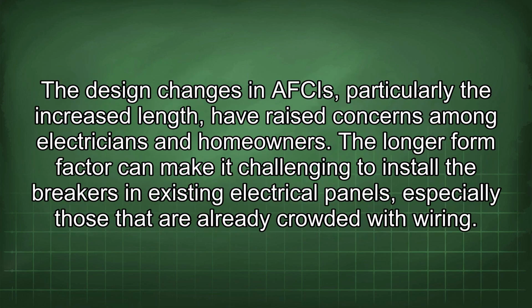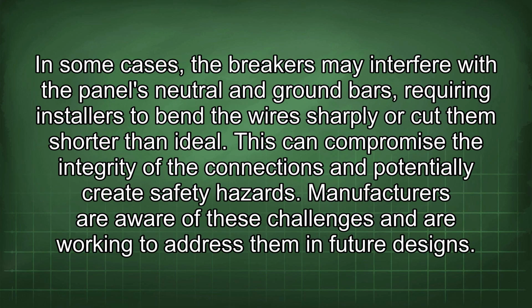The design changes in AFCIs, particularly the increased length, have raised concerns among electricians and homeowners. The longer form factor can make it challenging to install the breakers in existing electrical panels, especially those that are already crowded with wiring. In some cases, the breakers may interfere with the panel's neutral and ground bars, requiring installers to bend the wires sharply or cut them shorter than ideal. This can compromise the integrity of the connections and potentially create safety hazards.